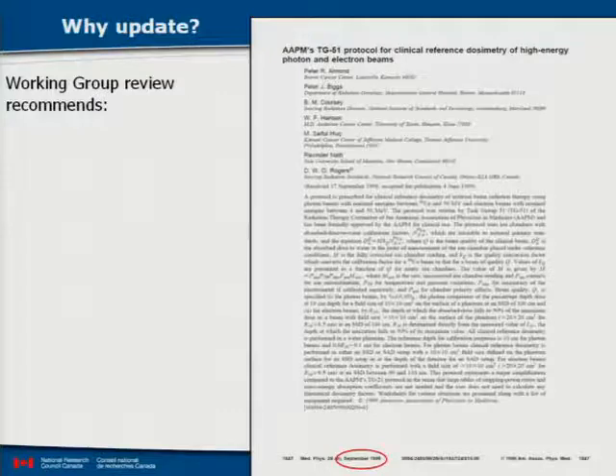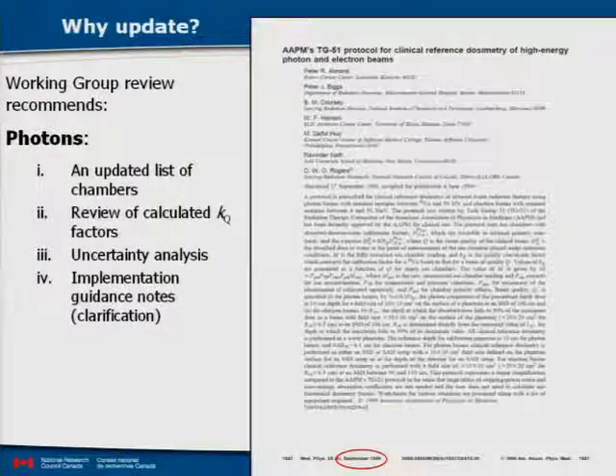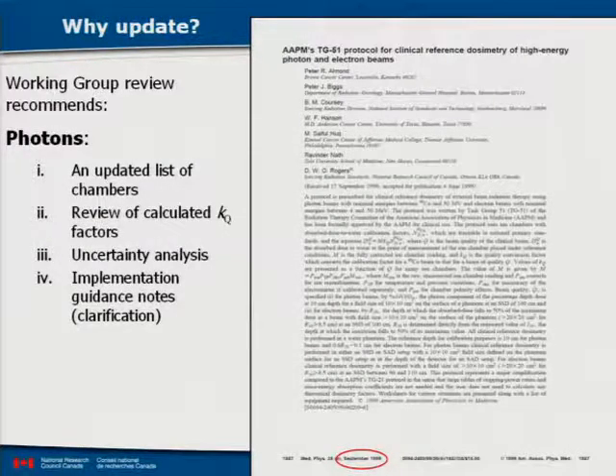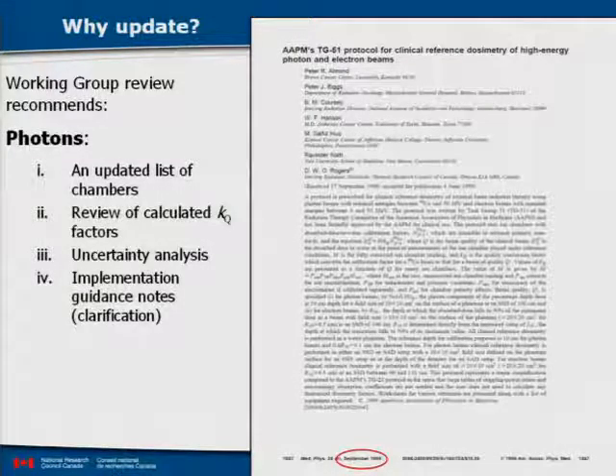Why update if it's so good or if it's been used everywhere? The real thing is the date — it's September 1999. So 12 years have gone by. It seems a reasonable time to ask whether it needs to be replaced. The working group has been formed, and it recommends the following. For photons, there are some updates required: new chambers have come on the market, we need a review of calculated KQs, an uncertainty analysis, and some AAPM official guidance clarification.